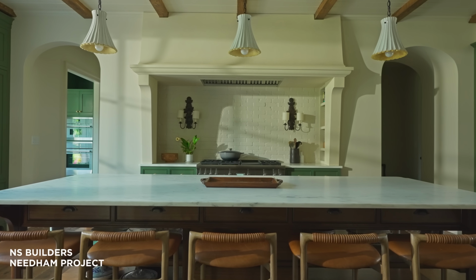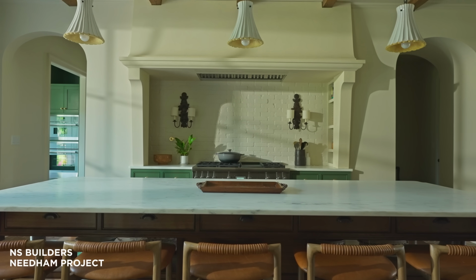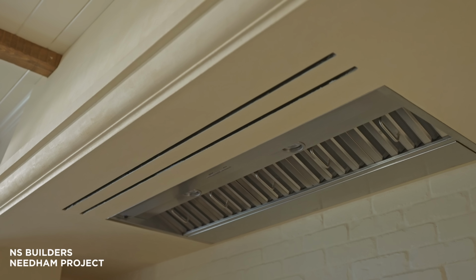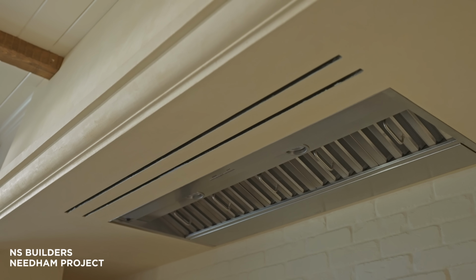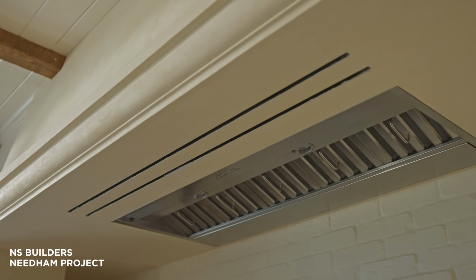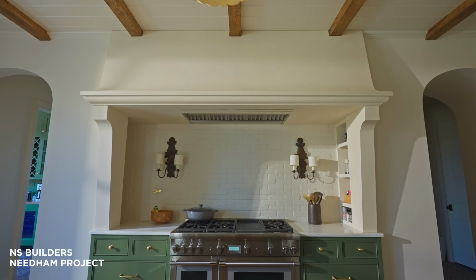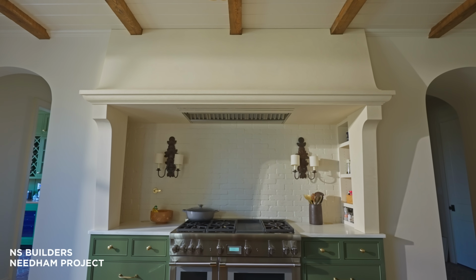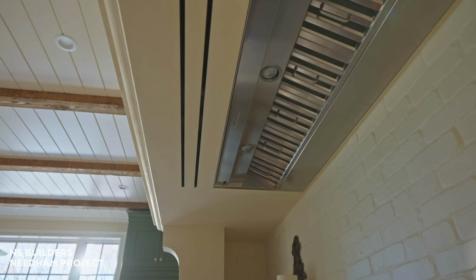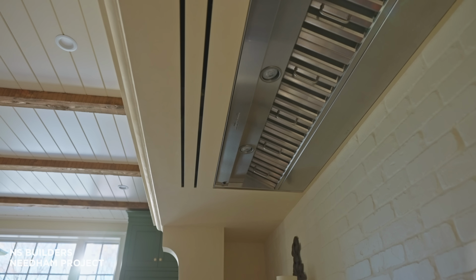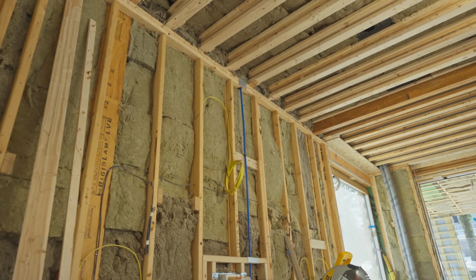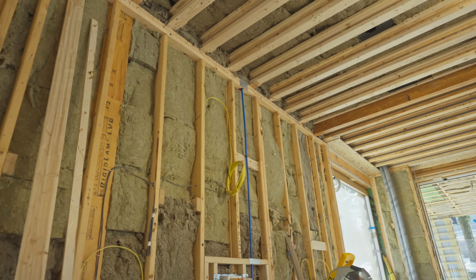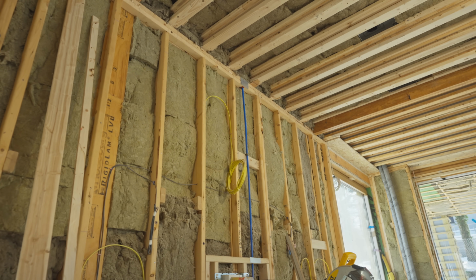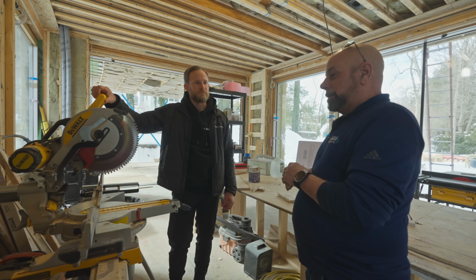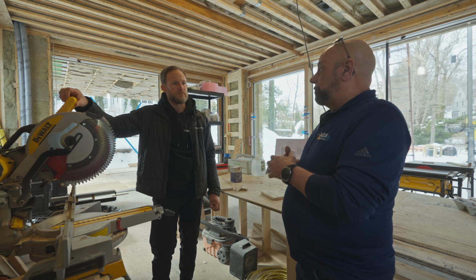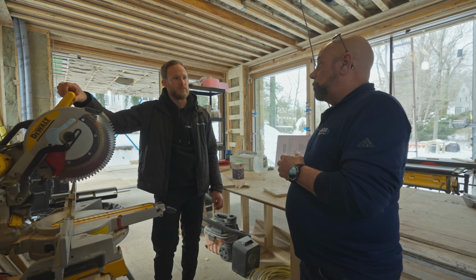It's almost like trying to suck the air out of a deflated balloon. Correct. A typical detail for us in all our projects is this hood within a hood, which is what we're doing here. Your exhaust air is going out, but we're bringing fresh air into the backside of the hood and filtering it, kind of like a commercial setup. So fresh air comes in, mixes with the kitchen exhaust, circulates and gets back up and out. There's no natural gas here, which is good. The most important thing is we're not creating negative pressure in the kitchen or house, and we're not taking from the heating and cooling system - that's why makeup air is important.